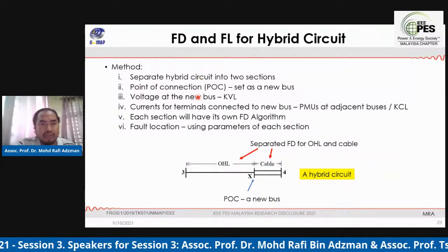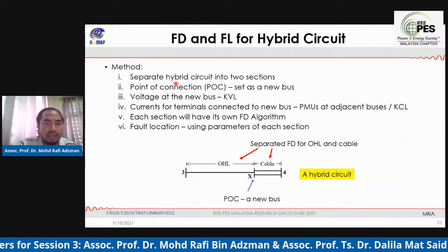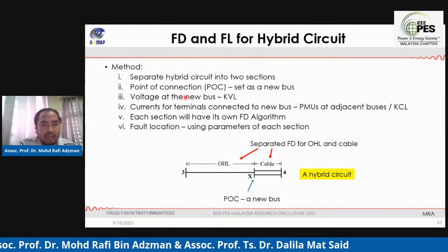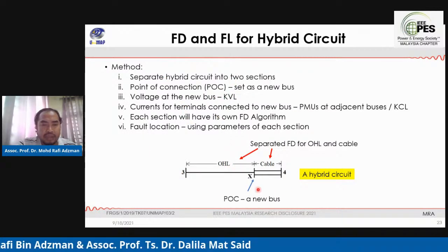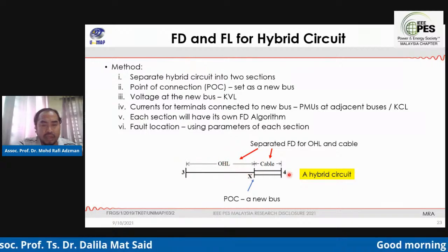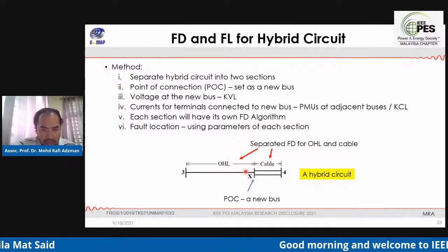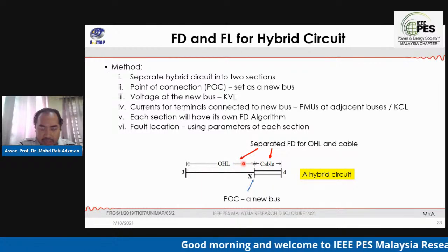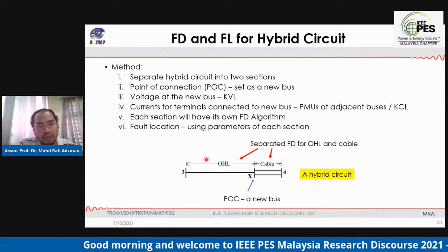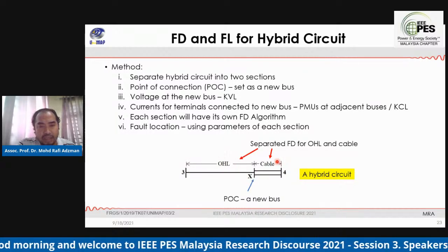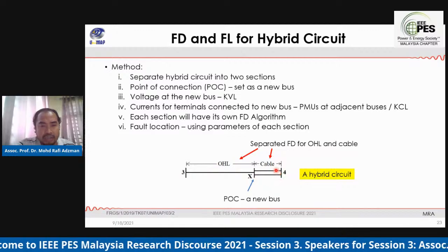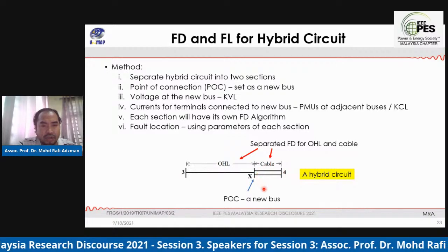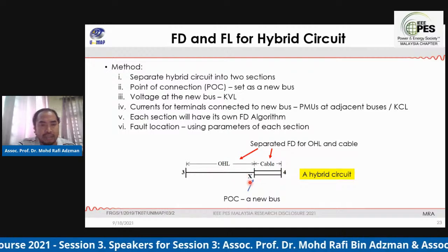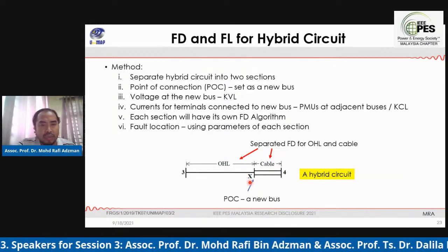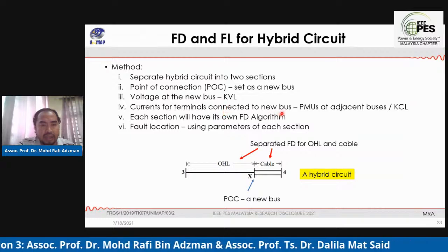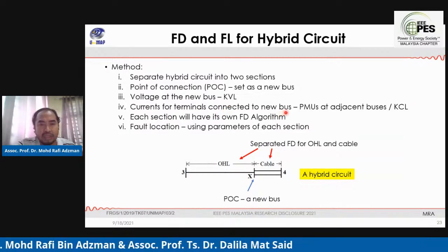Regarding fault distance and fault location for a hybrid circuit, in this method we separate the hybrid circuit into two sections. For example, in one line we have two kinds of lines: one is based on overhead lines, maybe bare conductors, and one uses cables. The point of connection is set as a new bus, and the voltage at the new bus is calculated using KVL, and the current using KCL.